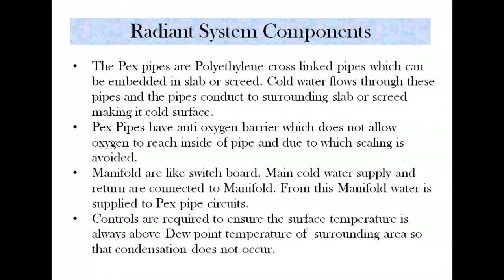Then the controls, as I mentioned, are required to ensure that the surface temperature is always above the dew point temperature of the surrounding area, so that condensation does not occur. PEX pipes are available in different sizes. It starts from 9 mm, 16 mm, 20 mm. We have 32 mm, 40 mm also. But generally, in a radiant system, 9, 16, and 20 are normally used.